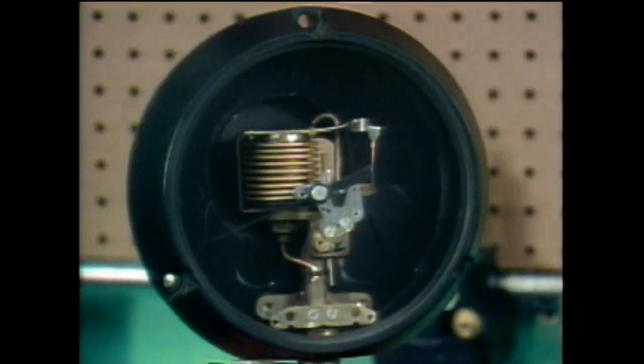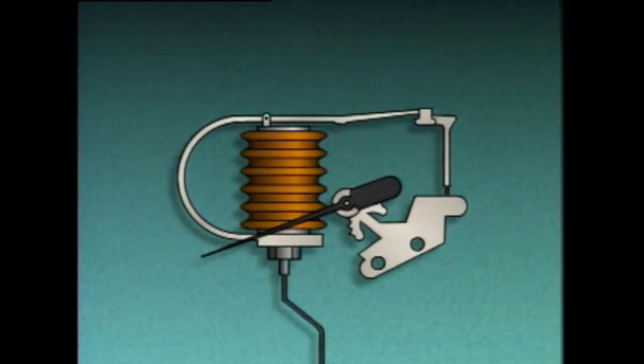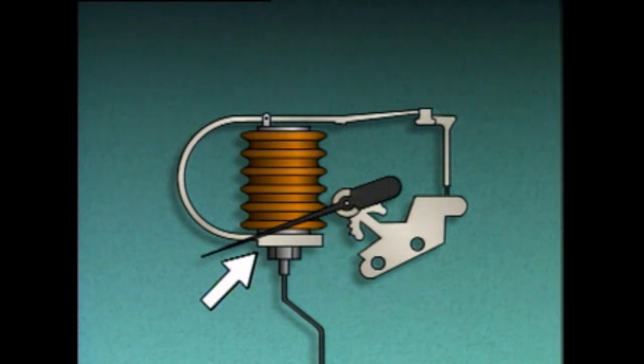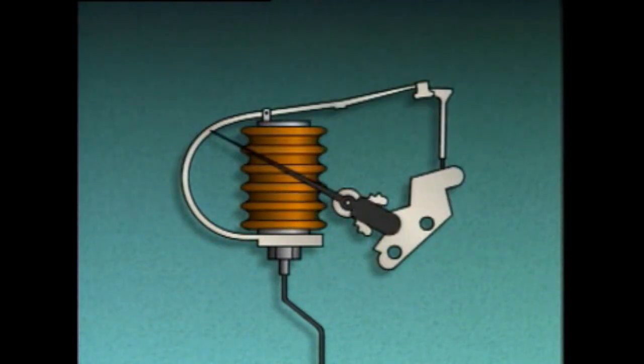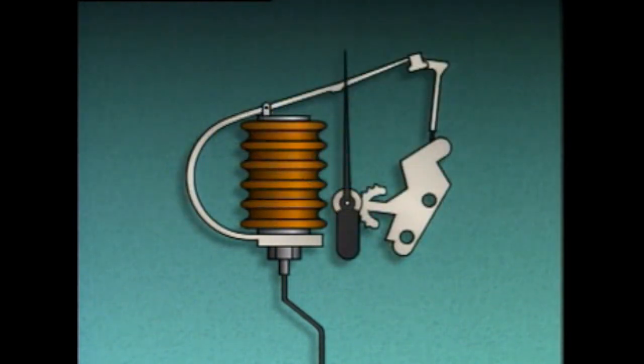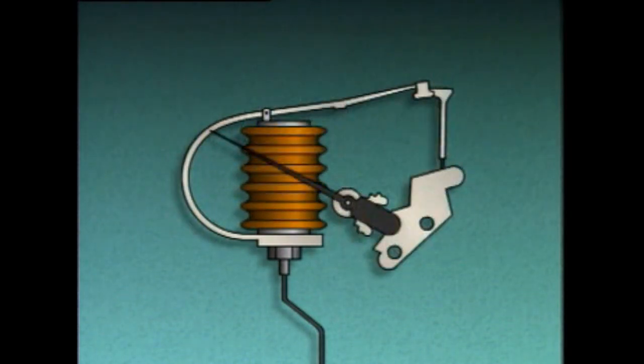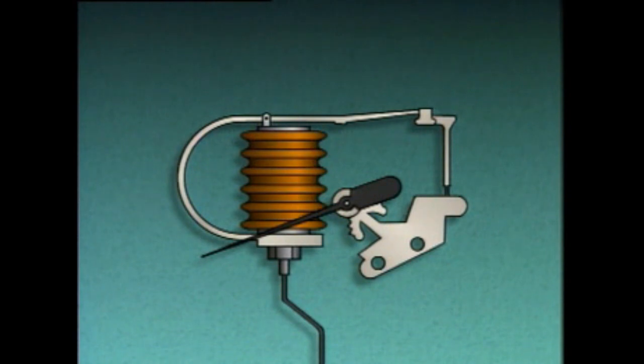Another type of pressure element that operates in a similar manner to a Bourdon tube is a bellows. In this arrangement, one end of the bellows is closed and the other end is connected to the pressure source. When pressure is applied, the bellows expands. As the closed end moves, it also moves a mechanical linkage which converts the movement to pointer travel. When the pressure is removed, the bellows contracts and returns to its original position.